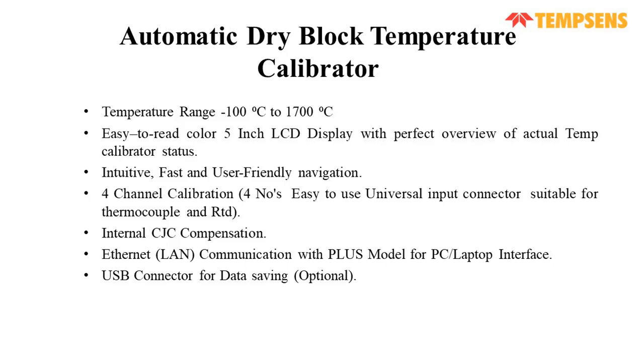Next, we'll come to the automatic dry block calibrator. It is available from minus 100 to 1700. All the models that I have discussed earlier are available in auto also. It comes with a 5-inch easy to read LCD display with a perfect overview of the actual temperature and calibrator status. It also has 4-channel calibration, 1 for the master and 3 for the test. And it has 2 modes, which I'll explain in upcoming slides.